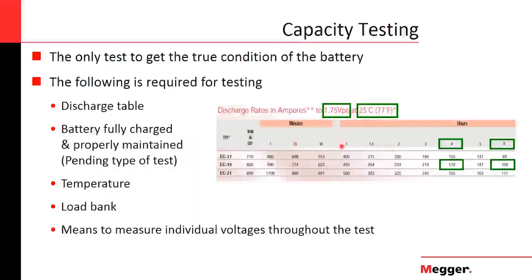And as you can see, for the example that I was using, this model is an 800 amp hour battery. So during 8 hours, you can draw 100 amps constantly. But if you want to get the same capacity of this battery in 4 hours, you need to use a different discharge rate. So definitely manufacturer tables are required to be able to perform an accurate test. You will never be able to run an accurate test without this table.